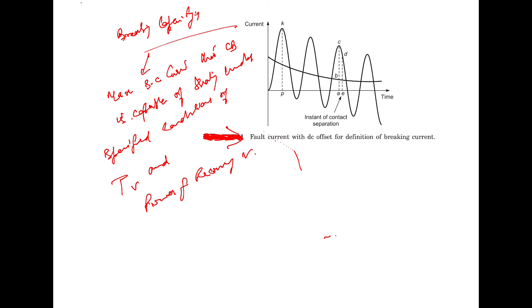Now, at the instant of contact separation, the circuit breaker current had a certain instantaneous value. However, this value is not designated as the breaking capacity, as you have seen. Instead, the breaking current refers to the RMS value of the current during the particular cycle in which the contact separation took place.